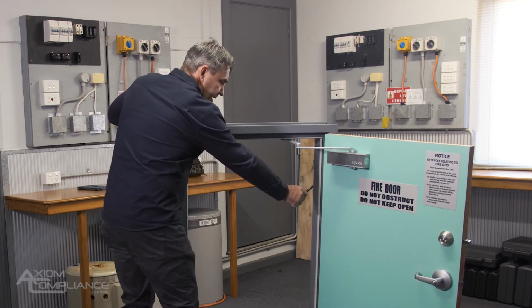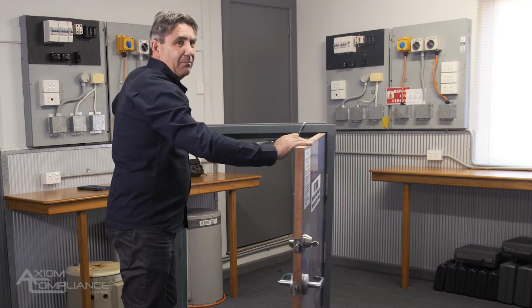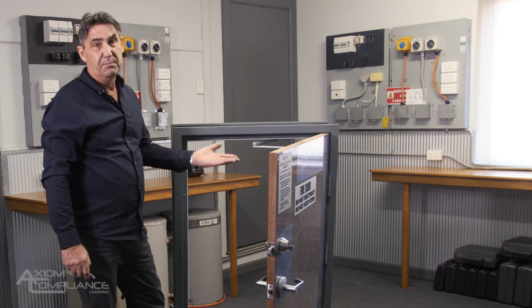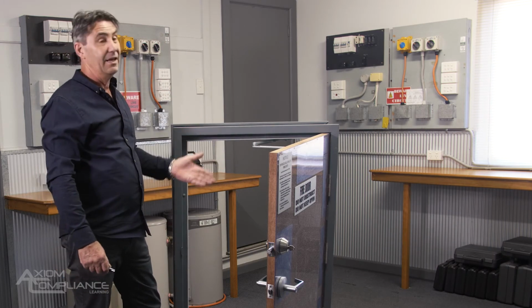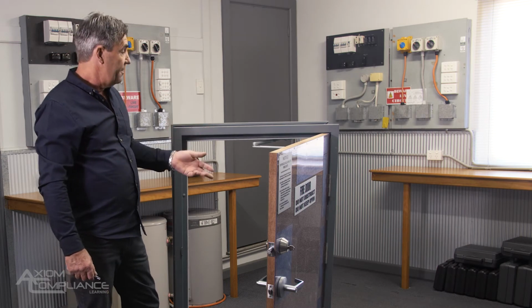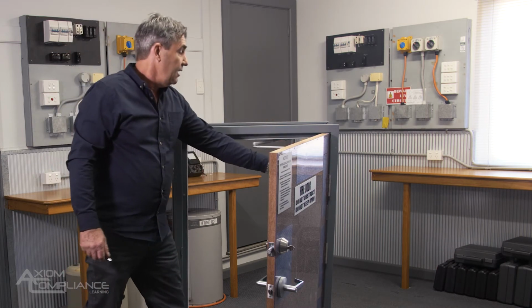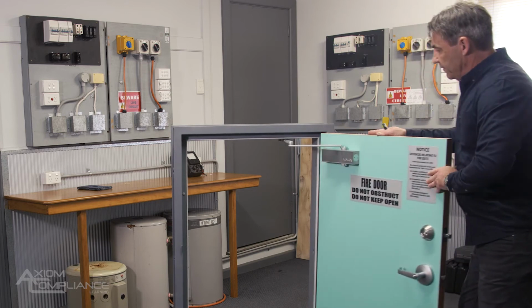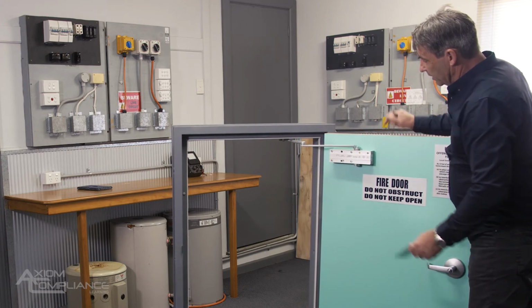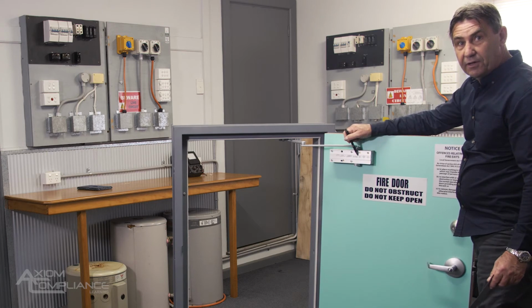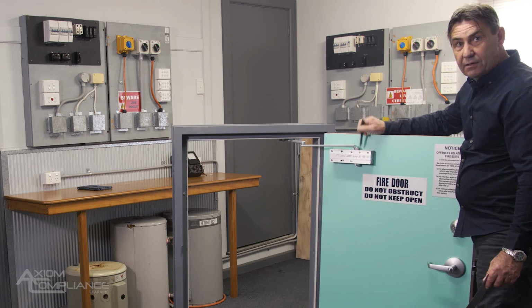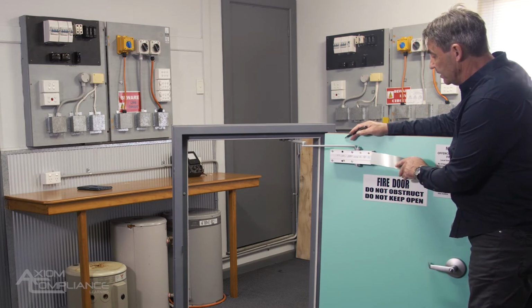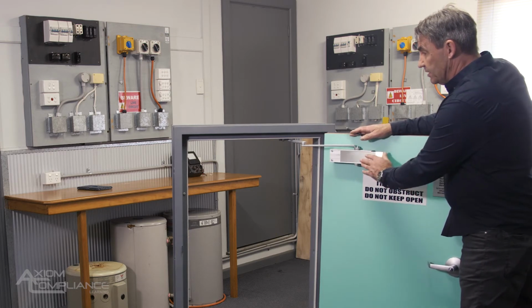Hinges are difficult because you don't really have a lot of marking on hinges. You've just got to look at the stainless steel hinge, make sure that it hasn't been changed, and to the best of your ability, determine whether that hinge is actually meant to be on that door. And then the third thing is your door closer. With a door closer, you can slide off the face and you can gain the manufacturer's information and the model numbers and everything on the door closer, and you can investigate that and find out if it is actually fire rated and designed for this particular door set. All right, so there's a lot to consider, isn't there?